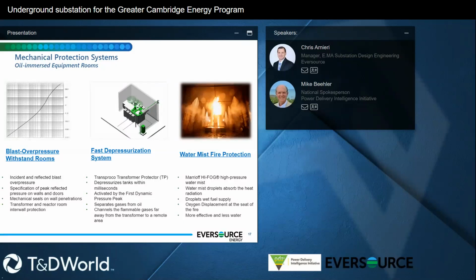And then last was our water mist fire protection system. This is a system that came to us a few years back, and we have successfully implemented this in outdoor stations. We've done it in a few indoor stations as well. It's a technology that we found from Marioff HI-FOG, what it's called, and it's basically a high pressure water mist system. What this does is there's a massive pump that takes a standard water line, like a 2-inch water line, and it builds pressure on that and comes out through these specialized high pressure nozzles that generate very fine mist droplets. Those mist droplets then hit the piece of equipment that you're trying to put the fire out on.